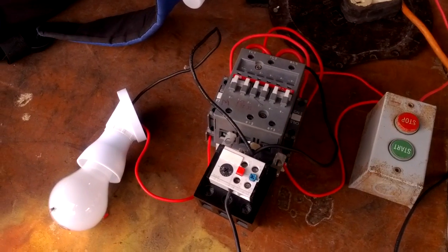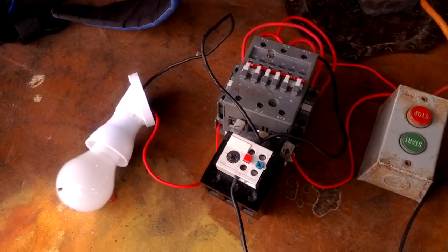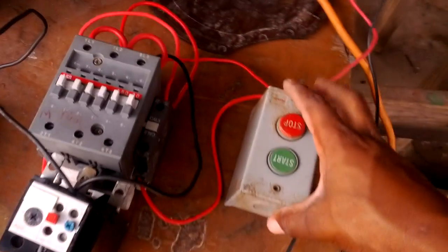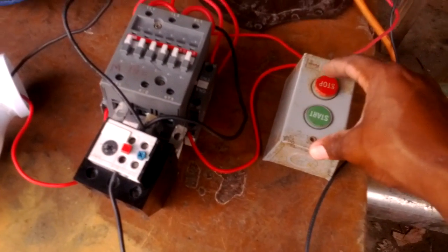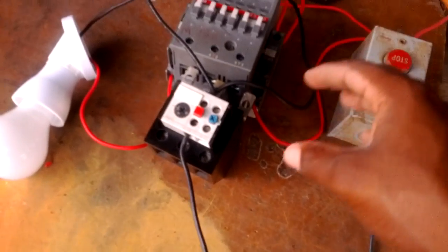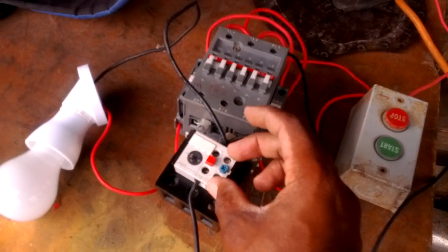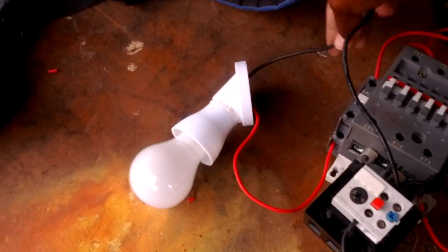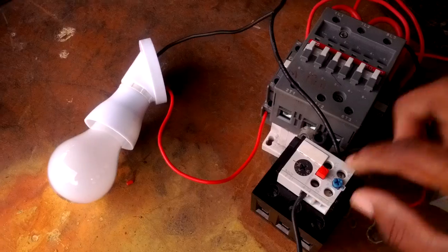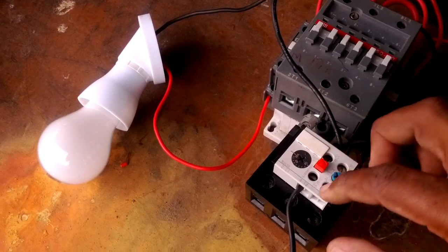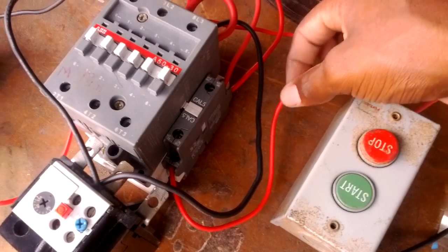And it's off again, and it's on. Now what you basically do is you come out of your stop button. I'm hoping you know how to wire stop and start buttons. What you do is normally you will go to your overload, the normally closed part of the overload with the neutral, and you go directly to your light. So my neutral goes directly to my light through the two auxiliary on the overload. That's the first thing you do.